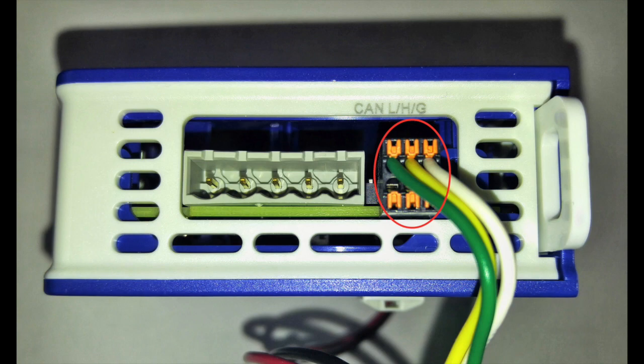The CAN ground wire is for common mode protection and is connected to the CAN ground, not DC or earth ground, of all other nodes on the network. Make sure to connect the CAN high, CAN low, and CAN ground wires to the connector.